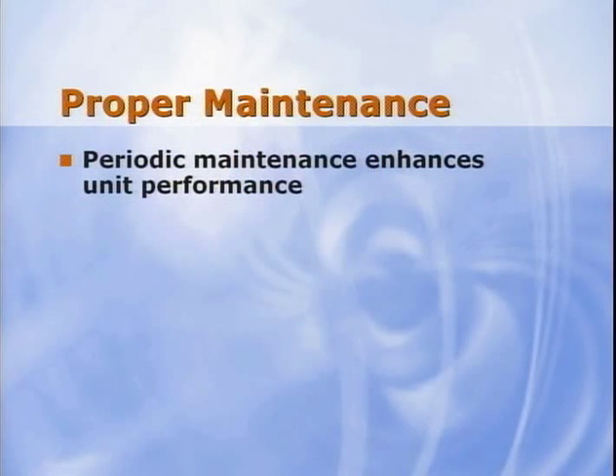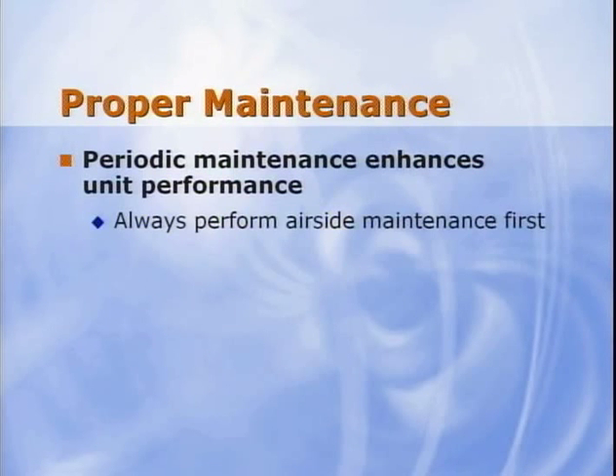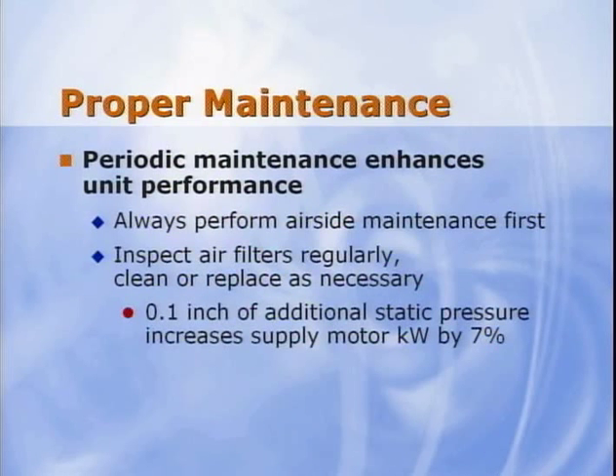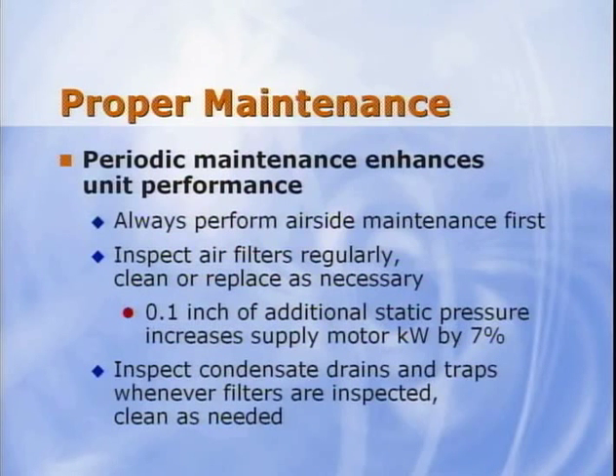Regularly scheduled maintenance helps to ensure continued energy savings benefits from your investment. Performing these often neglected preventative maintenance procedures can keep your system operating at peak performance. Remember to always have airside maintenance performed first. Airflows outside the design CFM can cause maladjustments to the refrigeration side. We recommend scheduling periodic filter inspections based on your application environment. Filters should be cleaned or replaced as necessary. An additional 1/10 of an inch static pressure drop induced by dirty filters can increase the supply fan kW by 7%. Inspect condensate drains and traps whenever filters are inspected and cleaned as needed.